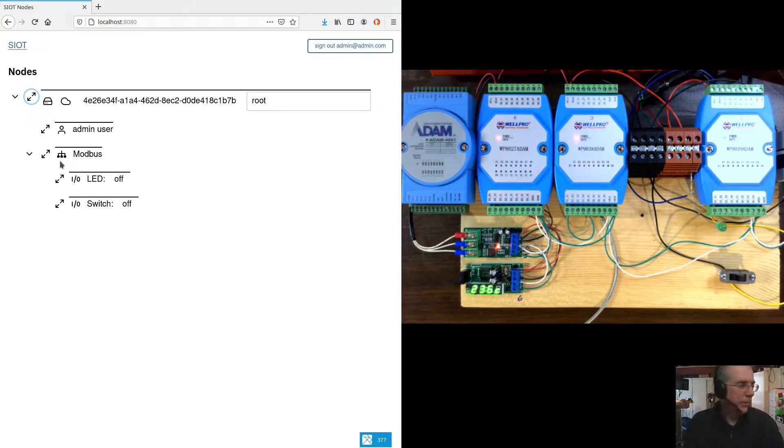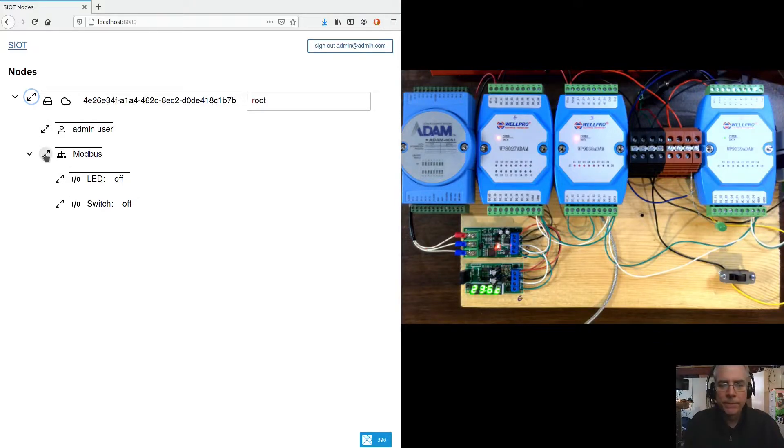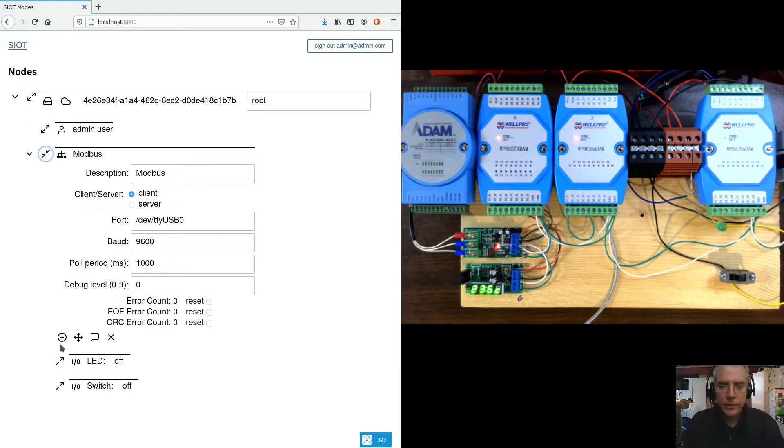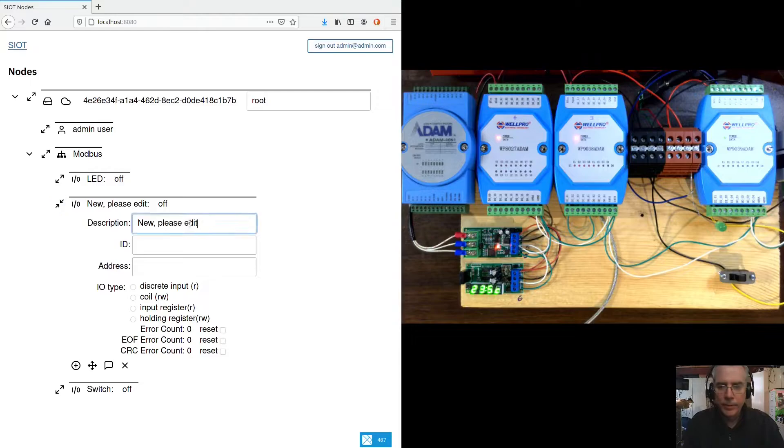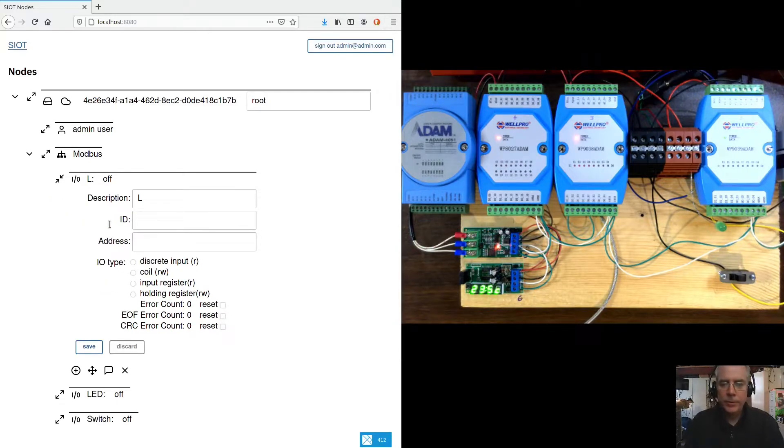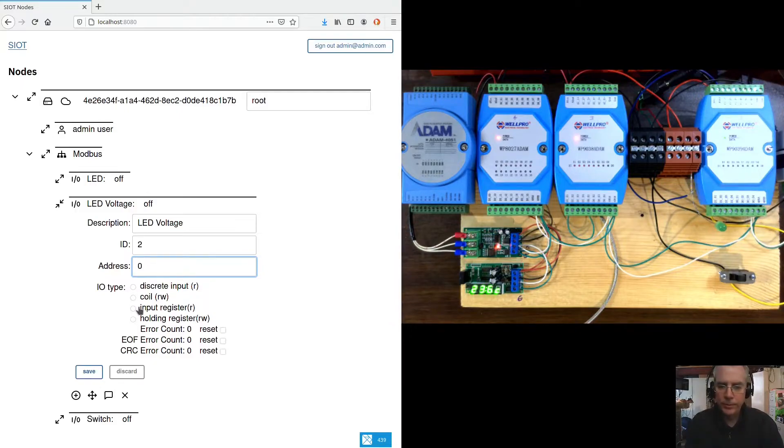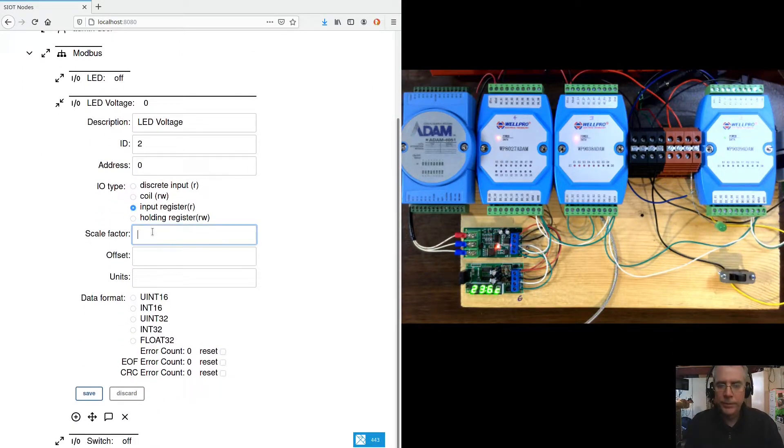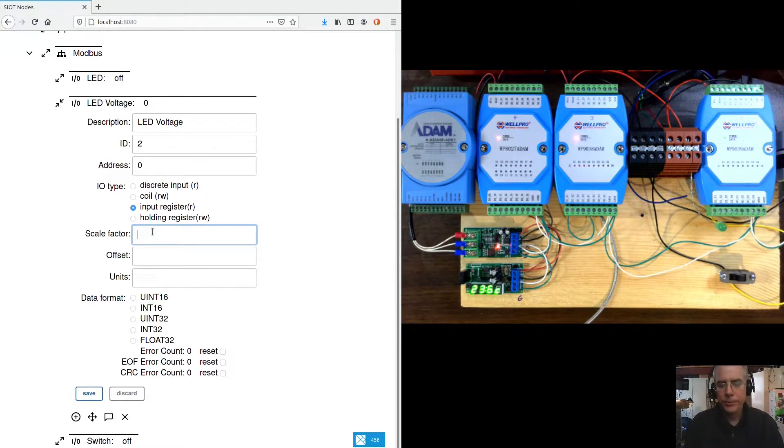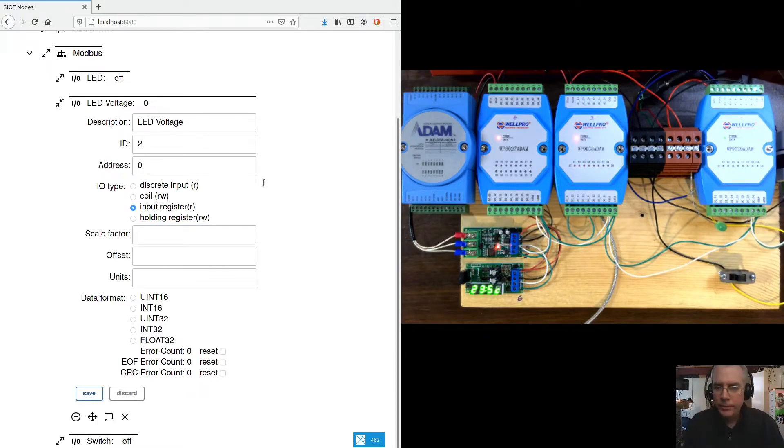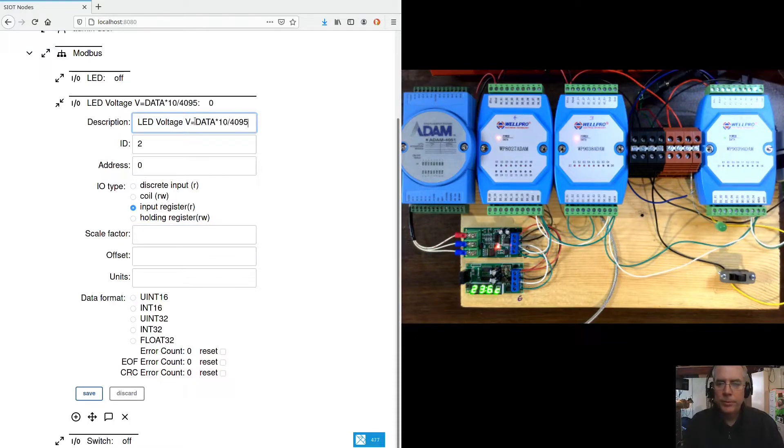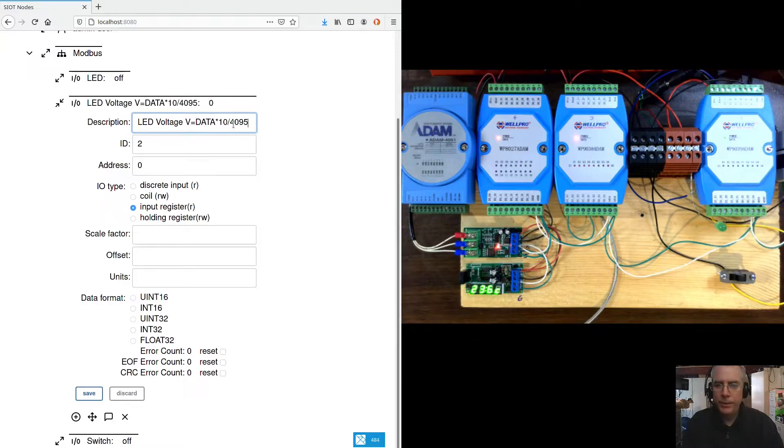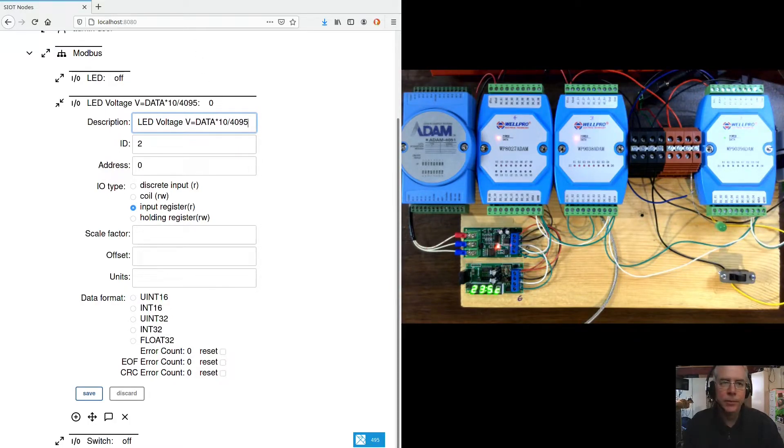This device here also has analog inputs and I have the first analog input connected to the voltage on the LED. So let's add another I.O. I'll call this LED voltage ID 2 address 0 because it's the first analog input. And the register value needs to be scaled to give us voltage. So the formula for voltage is we multiply by 10 and divide by 4095. So it reads from 0 to 10 volts and there's 4096 bits in the A to D. So that's where they get that.